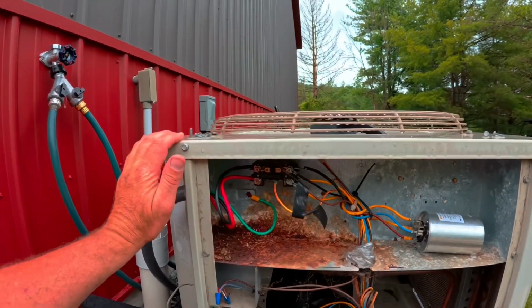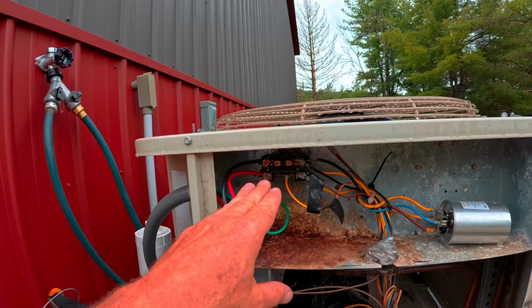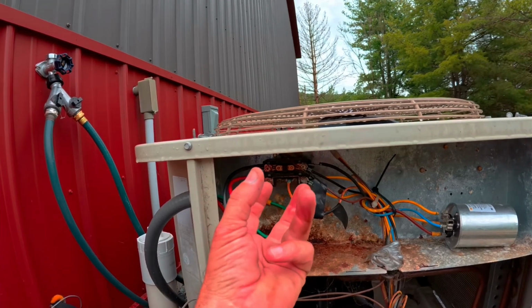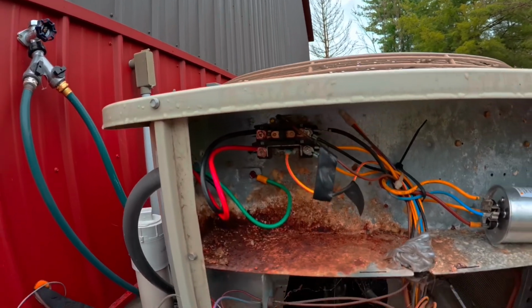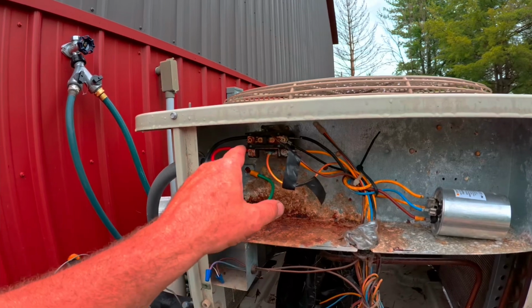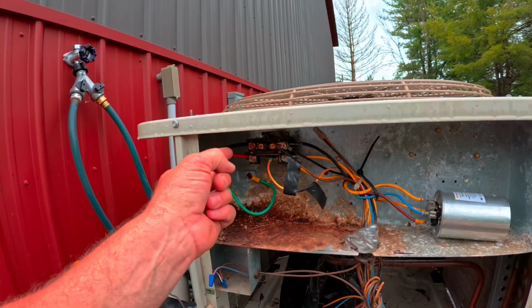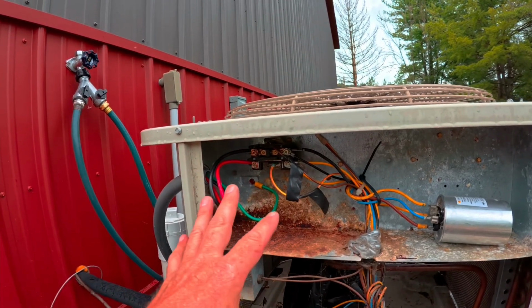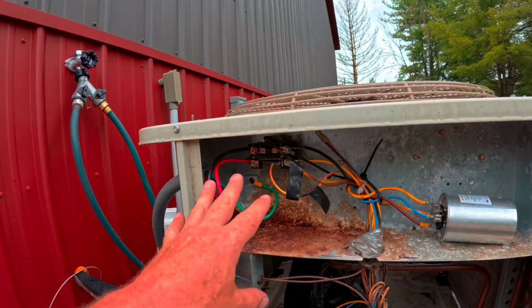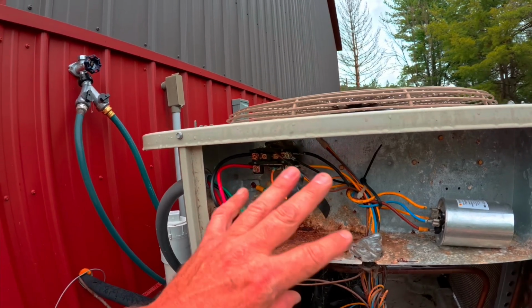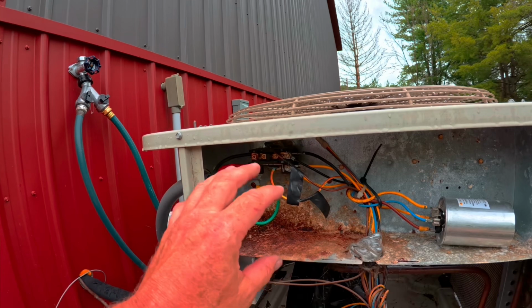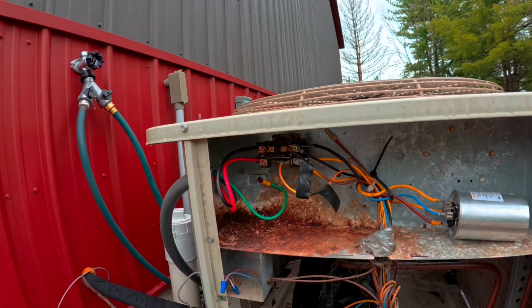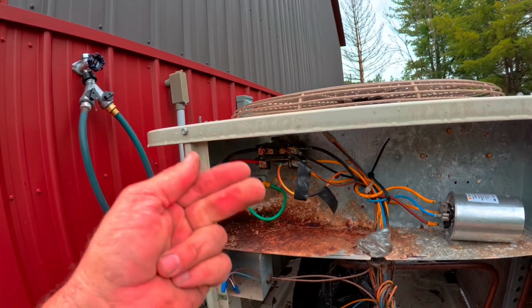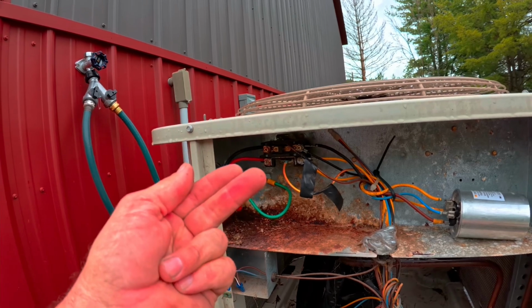They do fail. The other side of it, if it's not a bug in there, the contact points can actually just be corroded. And again, not allowing power to transfer through the switch. If that's the case, again, replace the contactor. They're not expensive. They're easy to replace after you shut the power off to the unit. That's shutting off the furnace and shutting off the main breaker for the air conditioning.